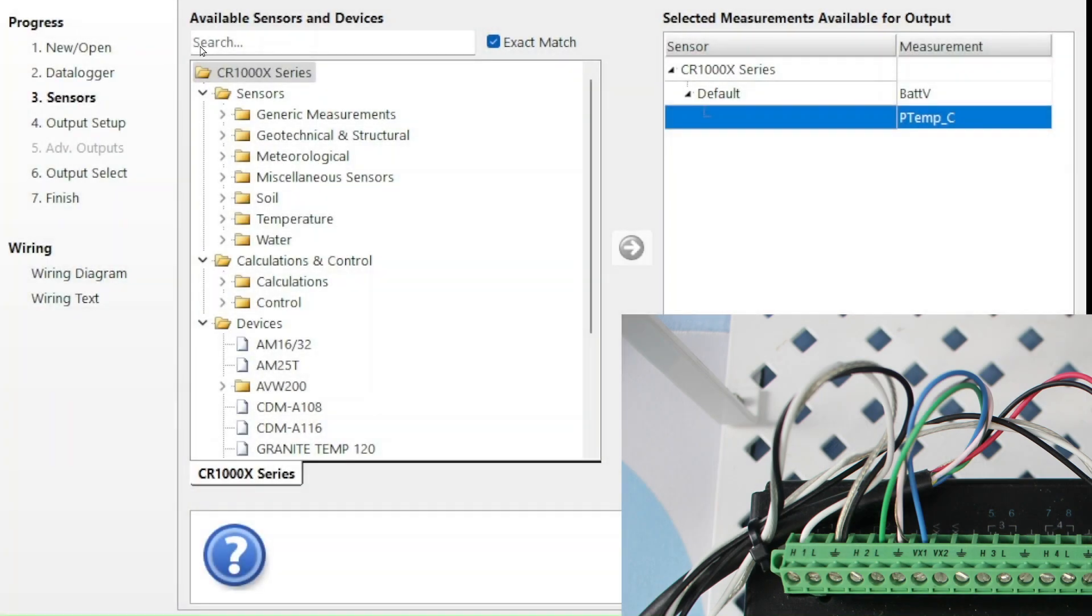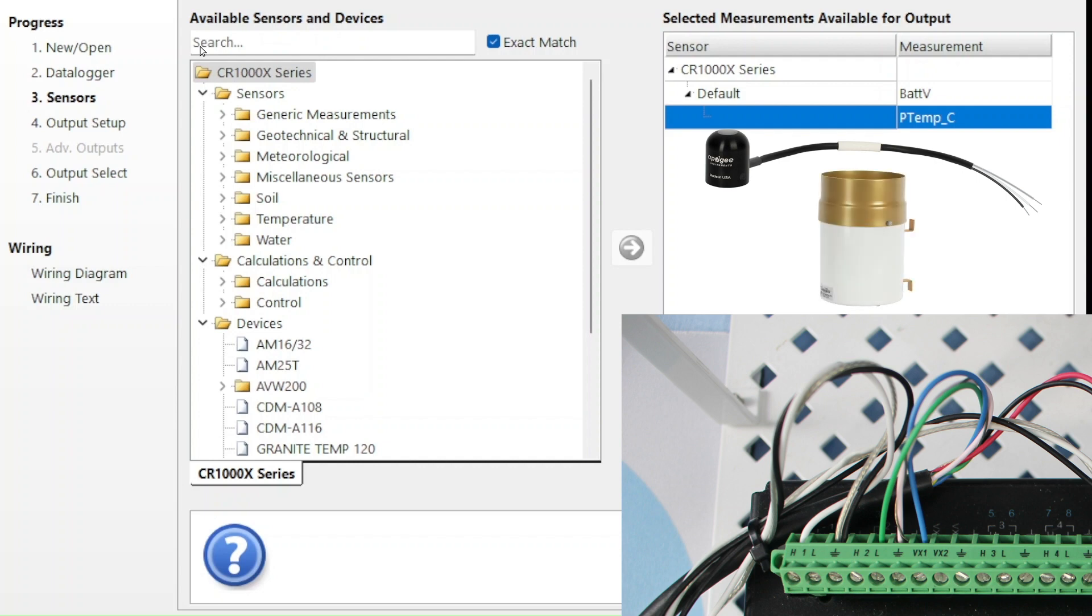My photo of the wiring panel shows that the sensor connected to channel 1H has white, black, and clear wires. Two of my sensors have wiring with those colors, CS301 and the TE525. If I'm not sure which one is connected to channel 1H, I can make a guess and see where SCWIN places the wires.